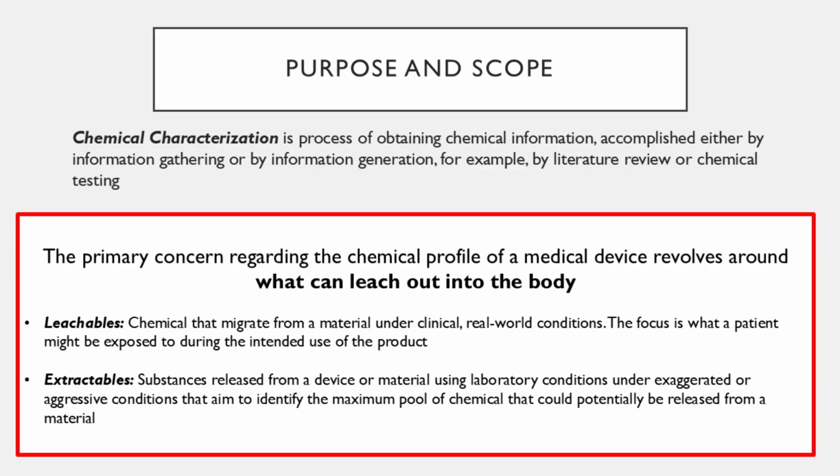Just understand that leachables is what is the real world condition, and extractables even has that sort of connotation of it's being forced. Someone has to extract something from the medical device, and that's exactly what we do in benchtop testing.